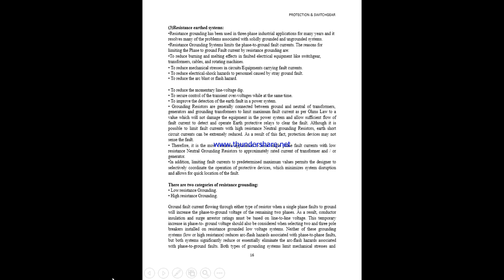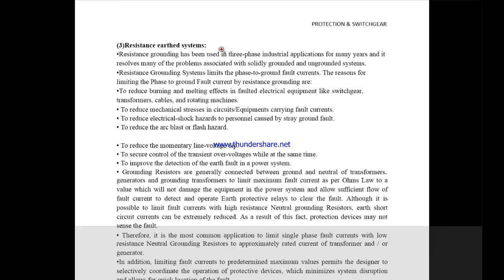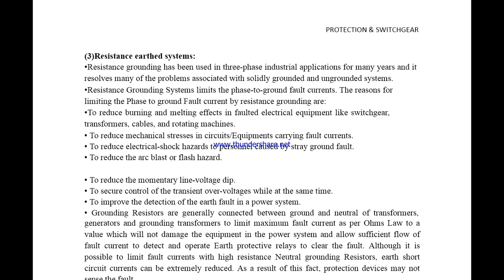While considering resistance grounding, a resistance is connected to the line from the neutral to the ground in order to reduce the burning and melting effects in the faulted electric equipment, to reduce the mechanical stress in the circuit, to reduce the electrical shock hazards, to reduce arc blast and flash hazard, to reduce momentary line voltage dip, to secure the control of the transient voltages, and to improve the detection of the earth fault. The grounding resistors act as per Ohm's law, so if the current is high, the voltage drops can be sufficiently managed with the help of these resistors.